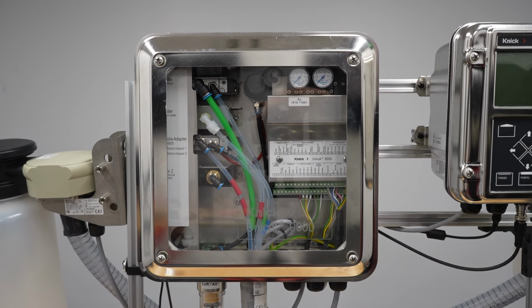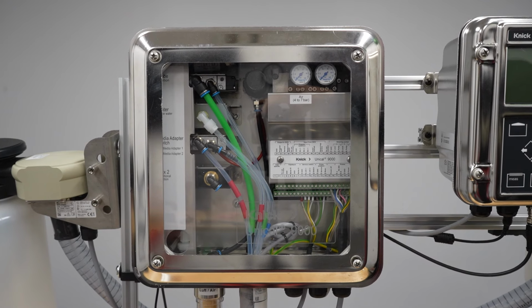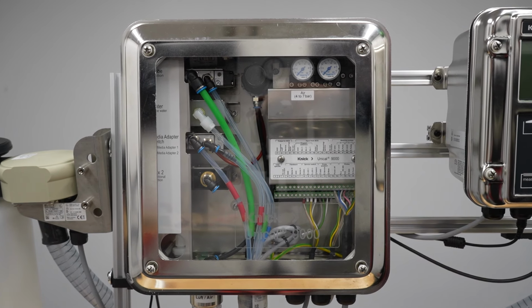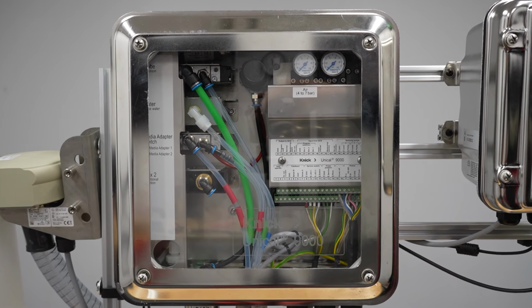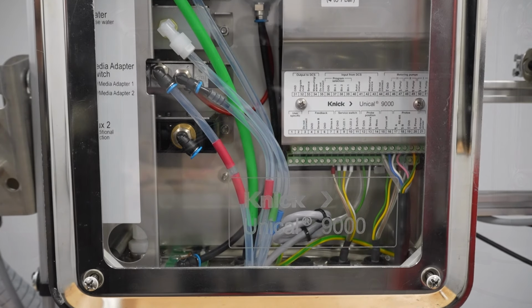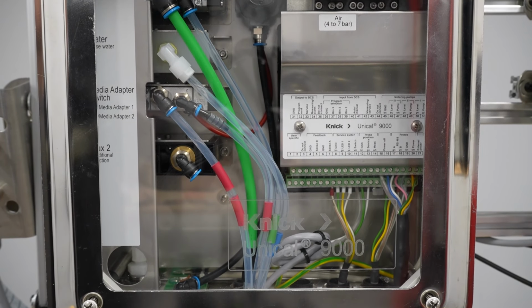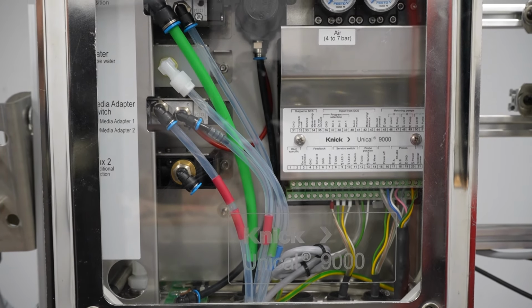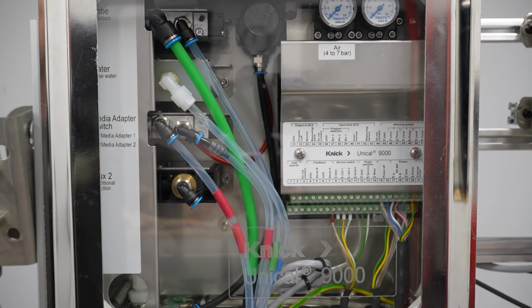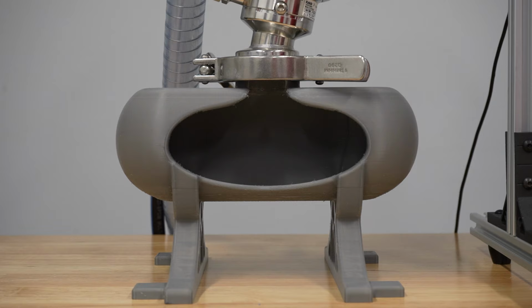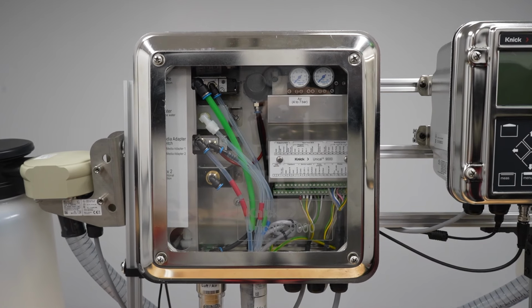The Unical pneumatic controller is what directs the various liquids based on what type of maintenance is required. If cleaning is needed, then the controller will signal for a cleaner to be pumped into the holder where the retracted pH sensor can be cleaned. If the sensor just needs to be stored during a plant maintenance turnaround, then the sensor can be stored in the holder with water to prevent the sensor from drying out.